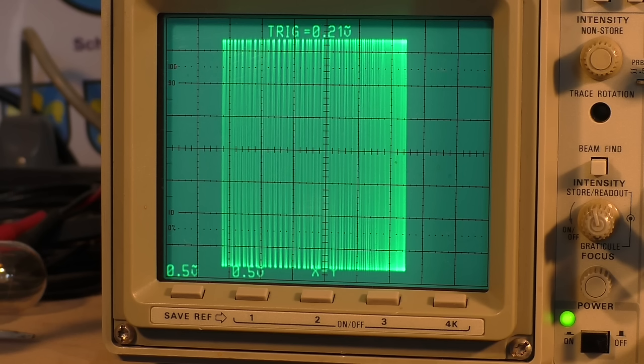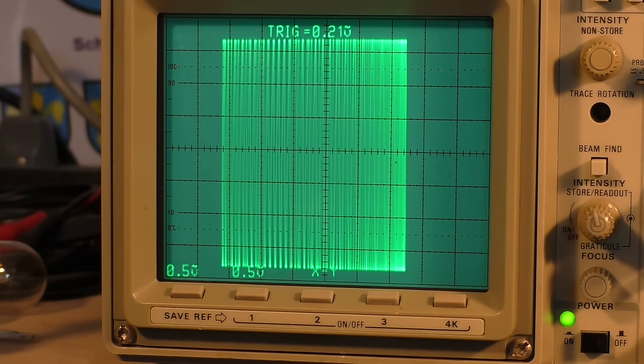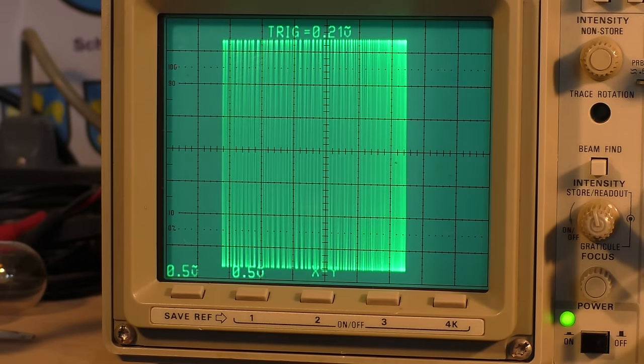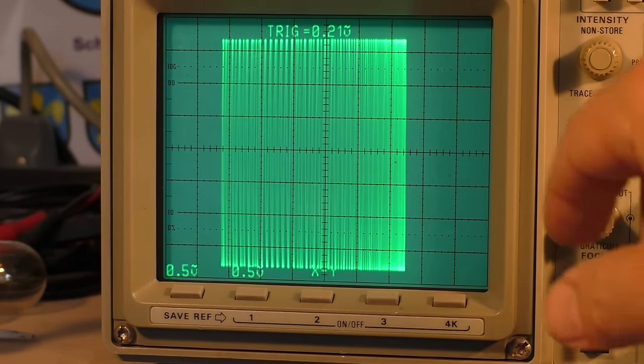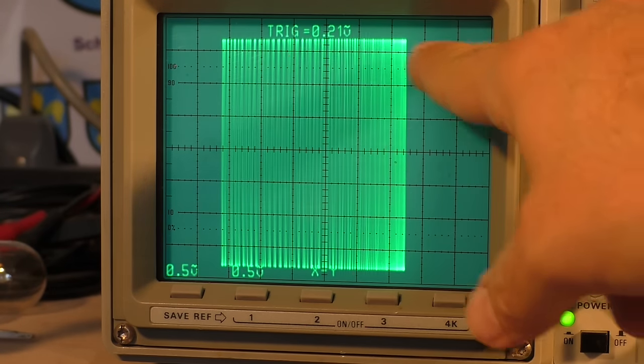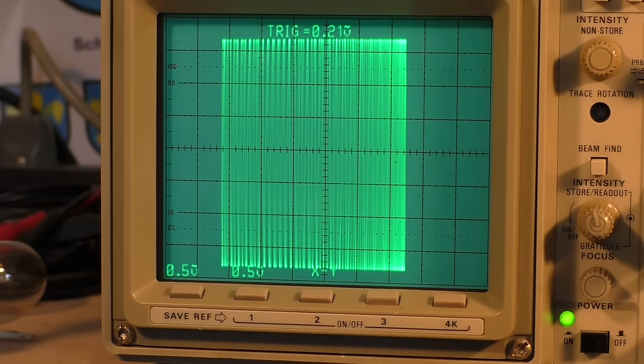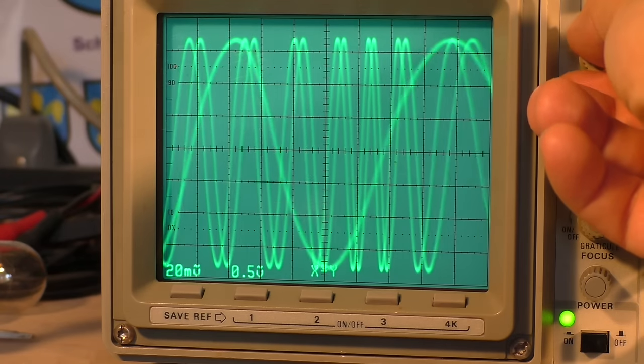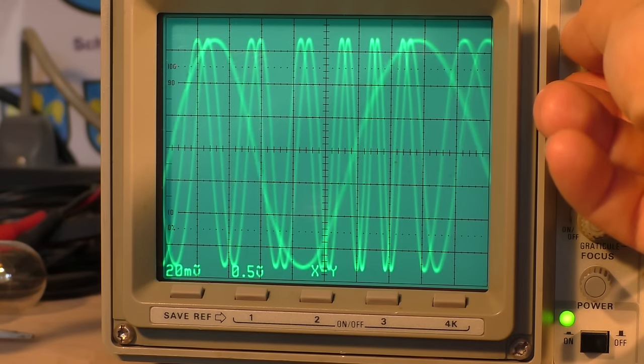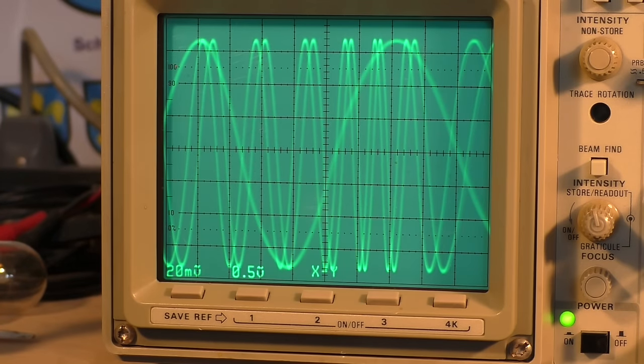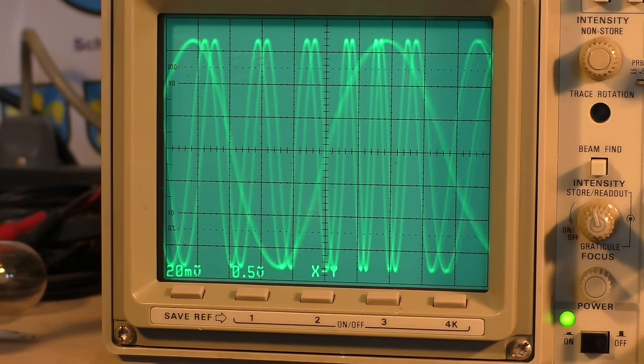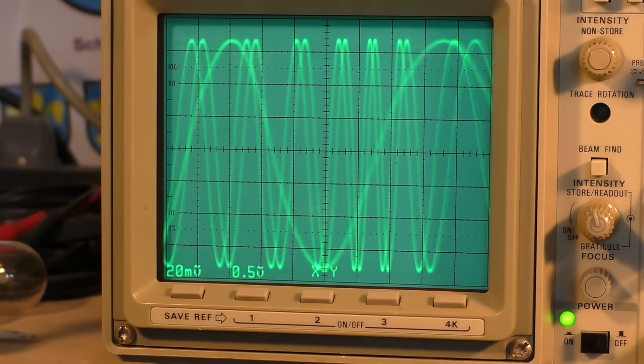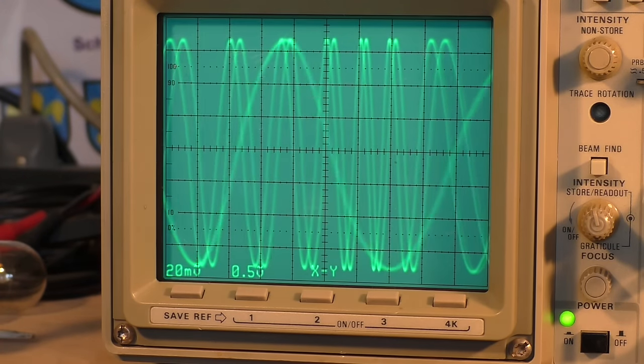In my case, the relations are 100 to one, so I have 10 megahertz for the rubidium clock or rubidium frequency standard, and we have 100 kilohertz for the Favag clock. If I would count them, I would see here 100 sine wave peaks. If I make them a little bit broader and a little bit brighter, you can see a small piece of the whole picture. As you see now, the sine waves are moving to the left or to the right, so I'm more or less on the right spot.